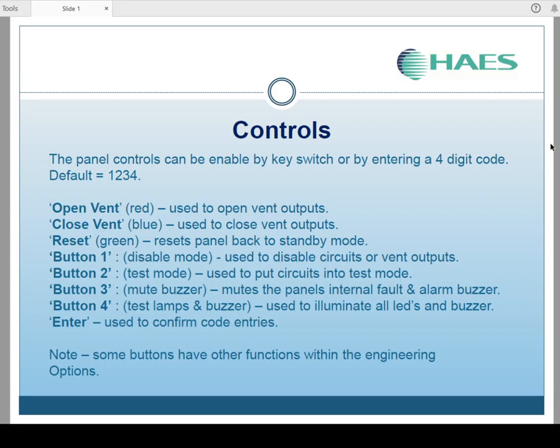Then below those you have button 1, also marked as disable mode, used to disable circuits or vent outputs. Button 2 is designated as test mode, used to put circuits into test mode for your weekly servicing or your annual servicing. Button 3 is your mute buzzer. This mutes the panel internal fault and alarm buzzer. Button 4, test lamps and buzzer, used to illuminate all LEDs and test the buzzer when you push that one. And then the enter button just to confirm any codes you've entered.